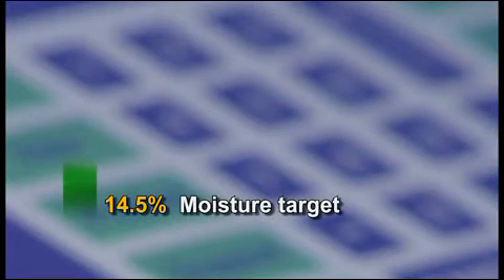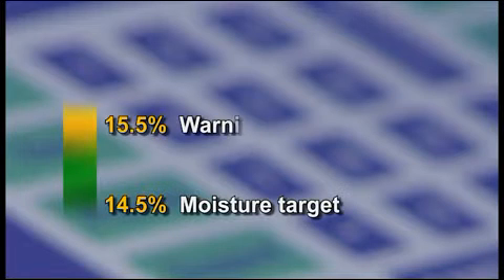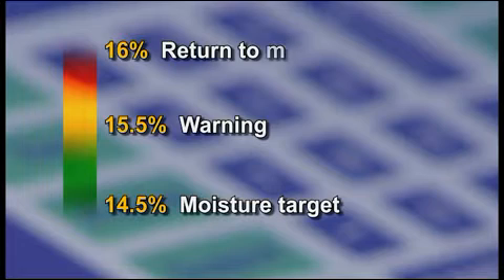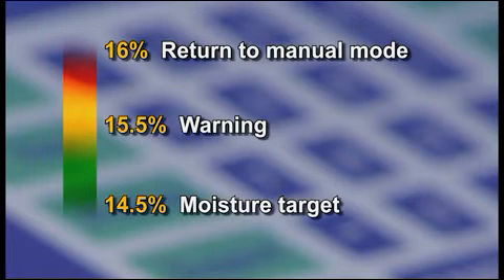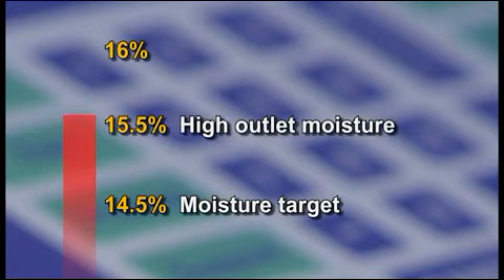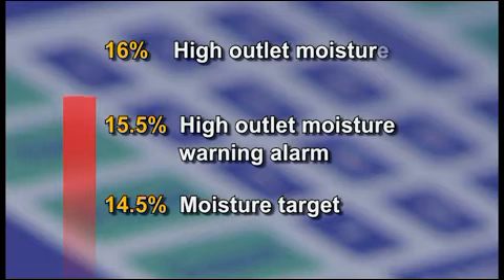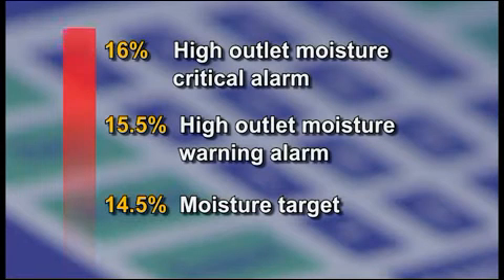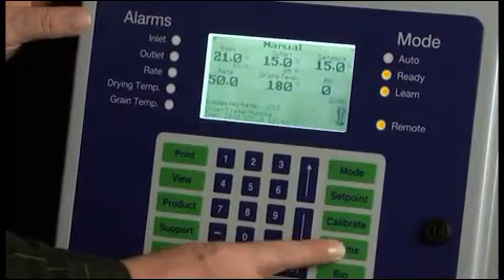We will use an example to show this relationship. Let's say that your moisture target is 14.5%, and that you want to be told if the moisture goes above 15.5%, and that if the moisture reaches 16%, you want the Dryer Master to stop controlling and return to manual mode. For this example, you would set your high outlet moisture warning alarm at 15.5% and your high outlet moisture critical alarm at 16%.